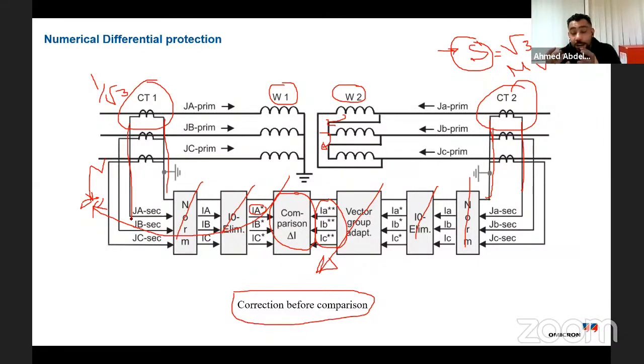So I defined the minimum operating differential current, but this is not enough, because there is a phenomenon that might happen beyond the CT ratio. It may happen due to CT saturation, or due to the magnetization of the current, which we'll talk about later. So I need to define a parameter to stop the relay from operating, like you are pushing the door to open, but someone behind it is blocking the door. You are trying to push to open the door to trip.